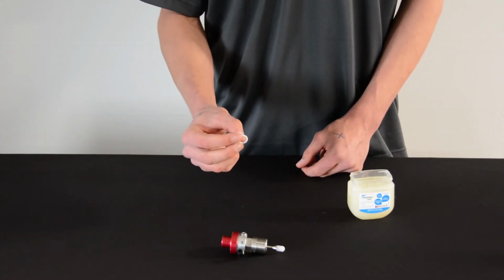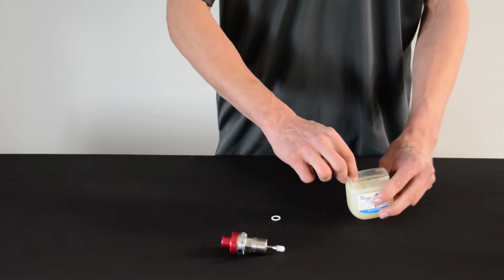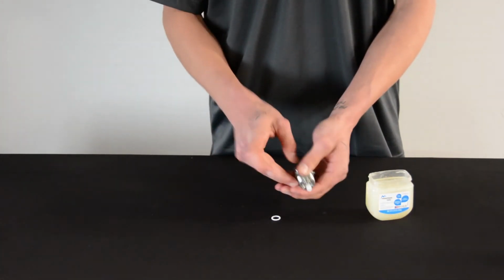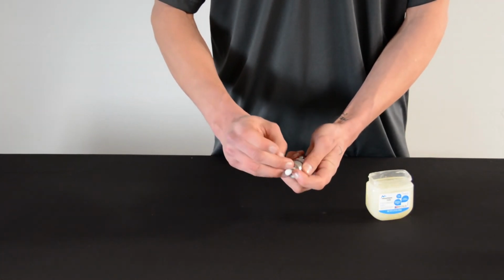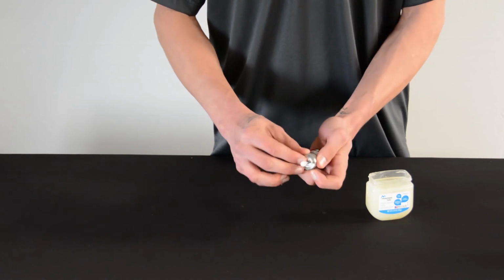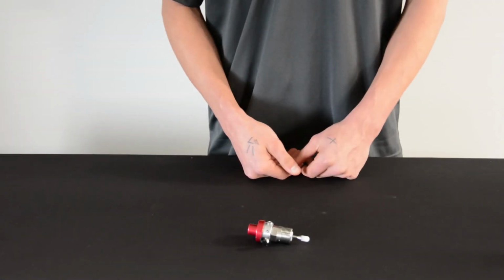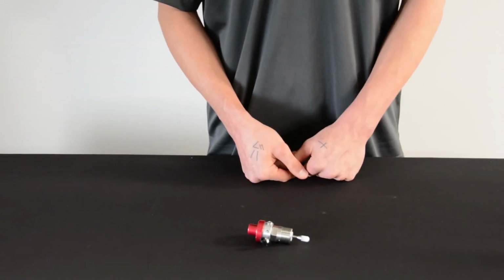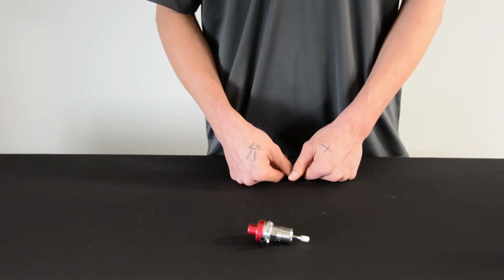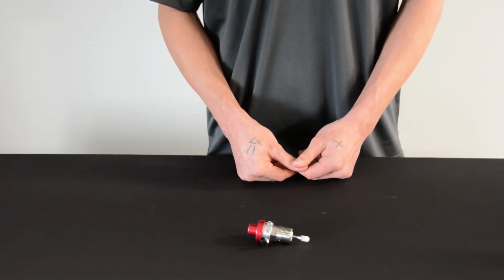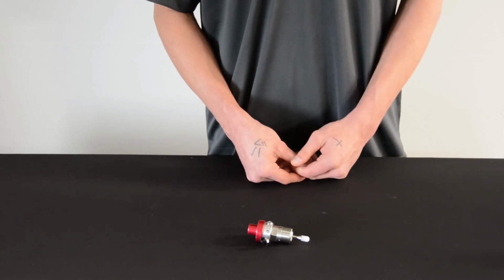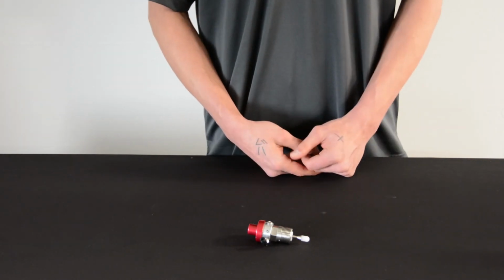Lastly, we're going to take our Teflon O-ring from the Poppet valve repair kit and a little bit of petroleum jelly and put it on the bottom of the valve body. Our Poppet valve is now completely rebuilt and it will need to be tested. It is important to remember that you don't put the Poppet valve back into use until 24 hours so the red Loctite on the plunger end can dry.